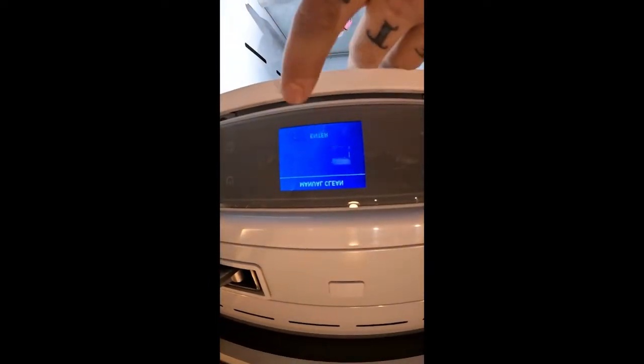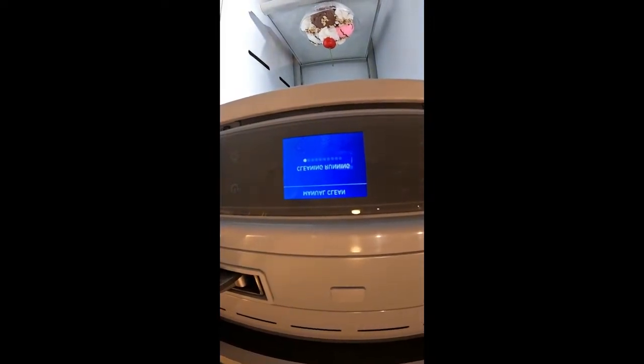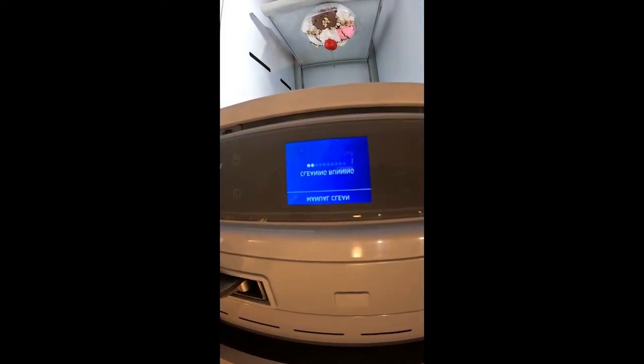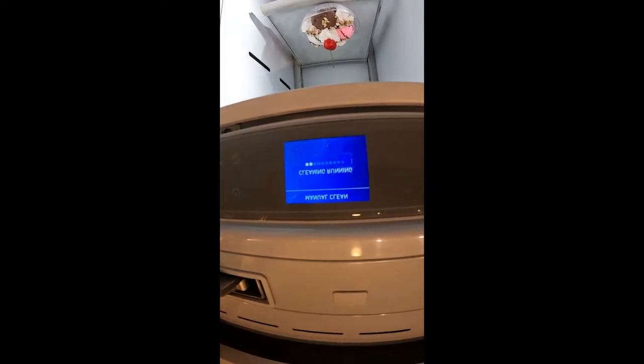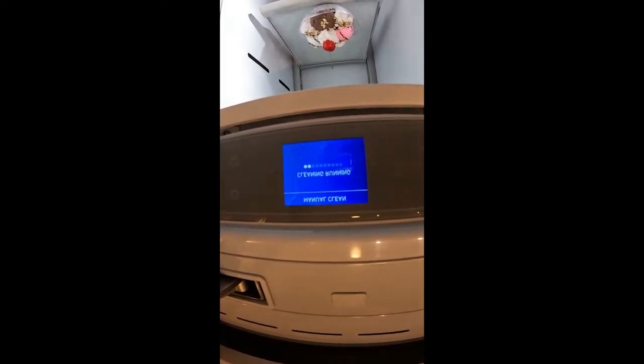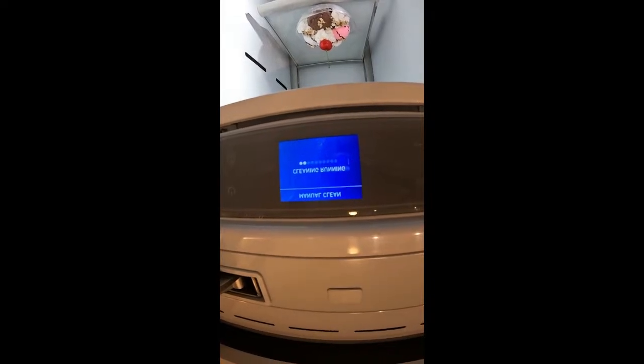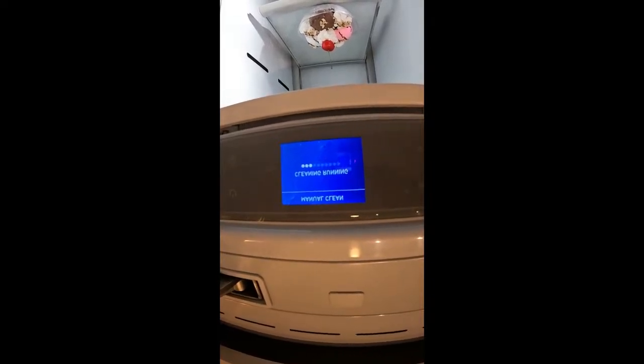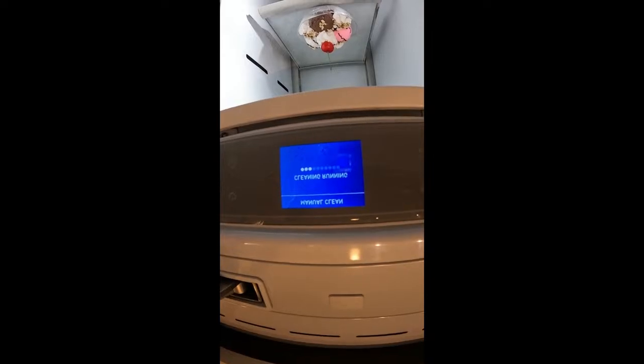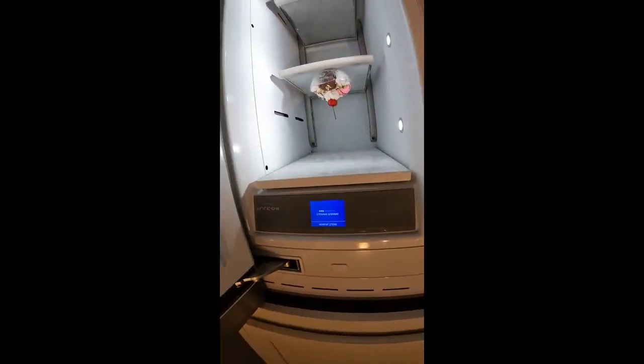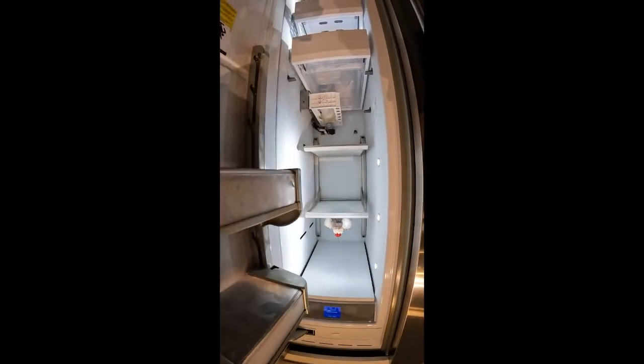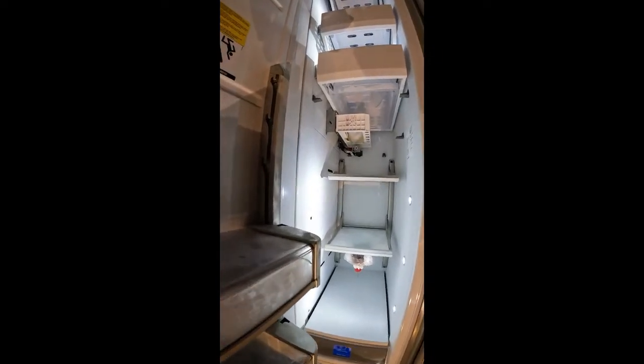We'll go ahead and push enter. You might be able to hear the valves humming at this point, and you can see a little countdown. It'll let you know when it's done. So at this point, both fill and safety valves are energized, and this ice maker should have water entering and flowing through it, trickling into the ice bucket. This particular machine is not plumbed, so we do not have water flowing at this point, but like I said, you can still hear the actual valves humming, where we should have water flowing.